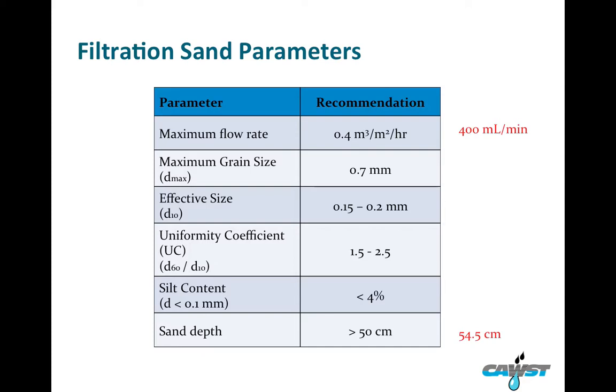Finding other ways to slow the filter down will help, and we've seen different ways that people have done this, but it won't solve these other problems. If your filter is fast, it means the sand is wrong. You should uninstall and fix the problem. If your flow rate is good, the other parameters probably are too. You can get the actual numbers by doing a sieve analysis.